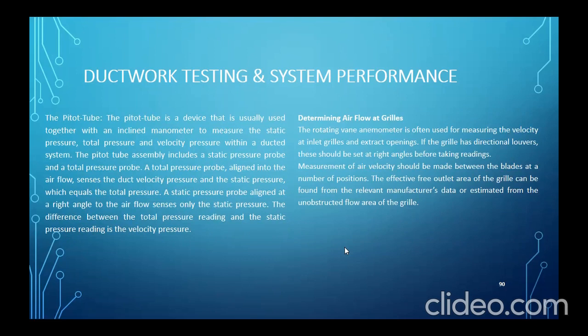The pitot tube assembly includes a static pressure probe and a total pressure probe. A total pressure probe aligned into the airflow senses the duct velocity and static pressure, which equals the total pressure. A static probe aligned at right angles to the airflow senses only static pressure. The difference between the total pressure reading and the static pressure reading is the velocity pressure.